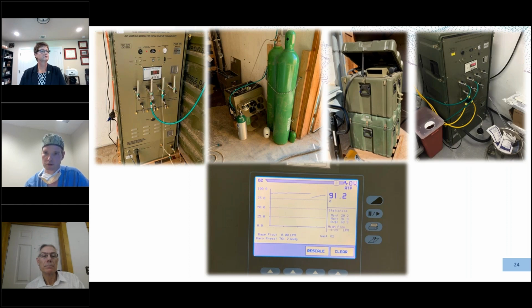The picture you see on the far right there is just another configuration. So this is actually from a training exercise. Same machine. We had the compressor outside, as mentioned before, so it had plenty of flow of air, and because it was so loud. But you can actually have the generator itself in patient care spaces. So that's actually our operating room in one of our field hospitals, one of our tent hospitals. And we actually had piped in the medical air and the oxygen right into the anesthesia machines, and we ran them just right off the generator inside the operating room.